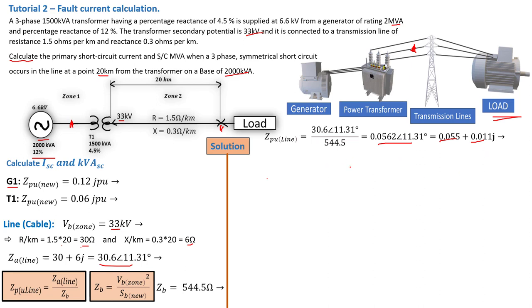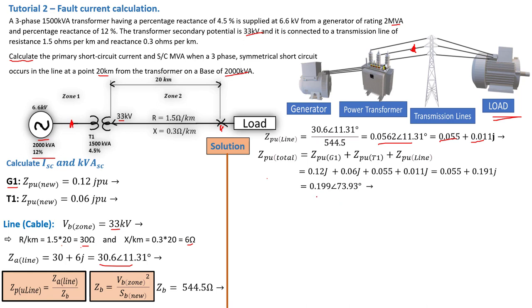To calculate the short circuit current, we need the total per unit impedance — the sum of the per unit values of the generator, transformer, and transmission line. Z per unit total = Z generator + Z transformer + Z line, giving a total per unit impedance of 0.199 at an angle of 73.9 degrees — essentially 0.2 at 74 degrees.